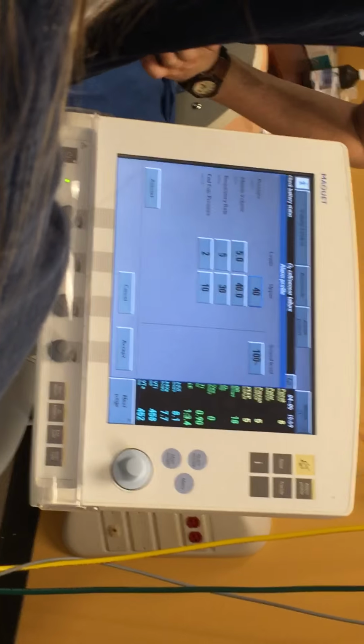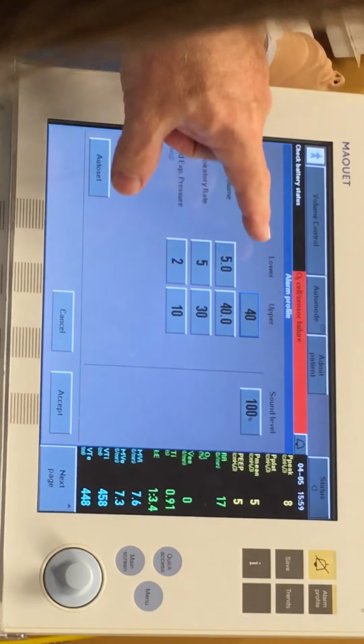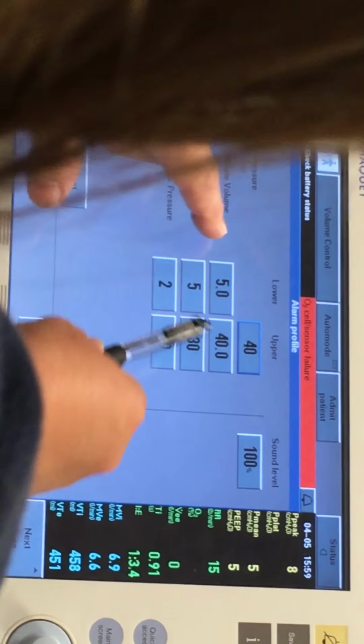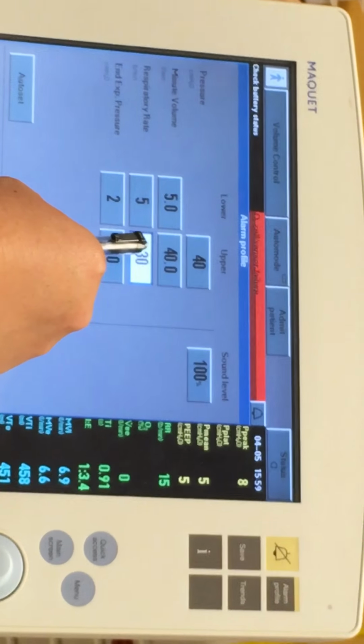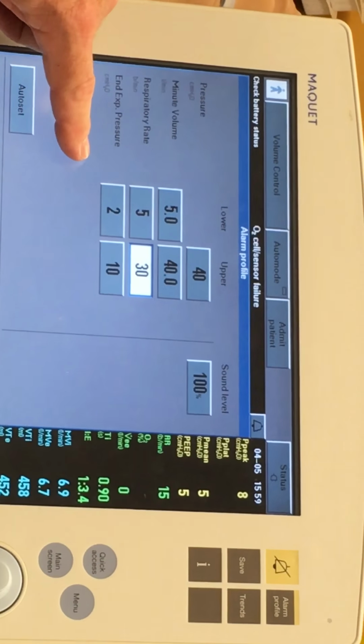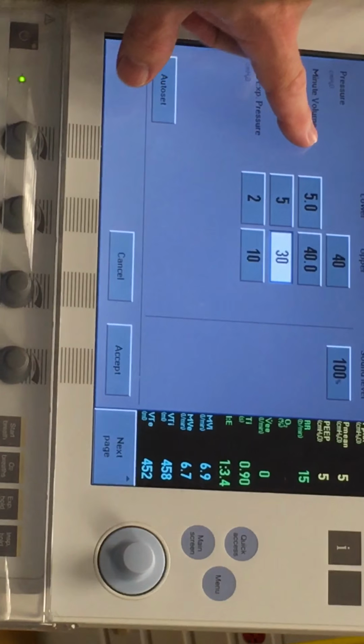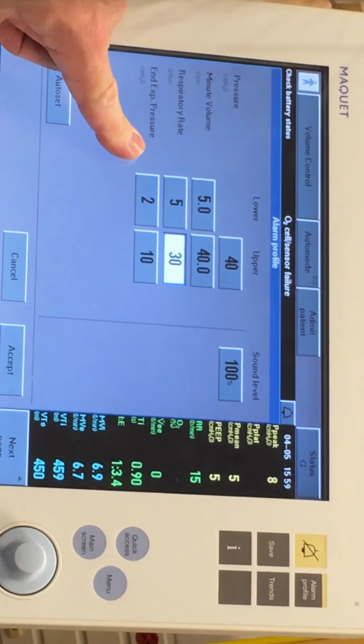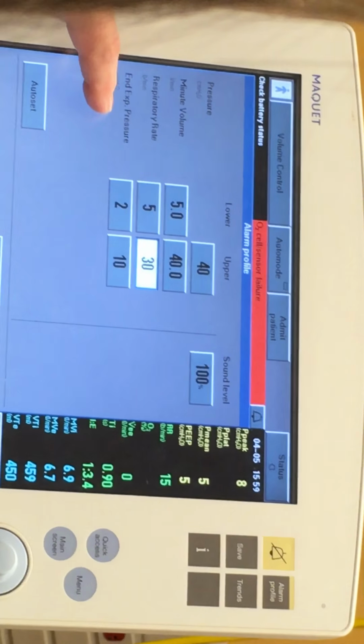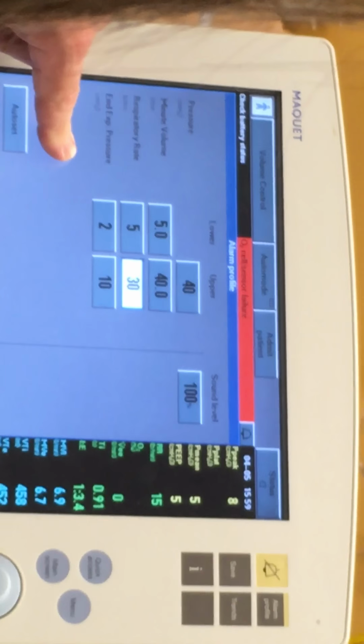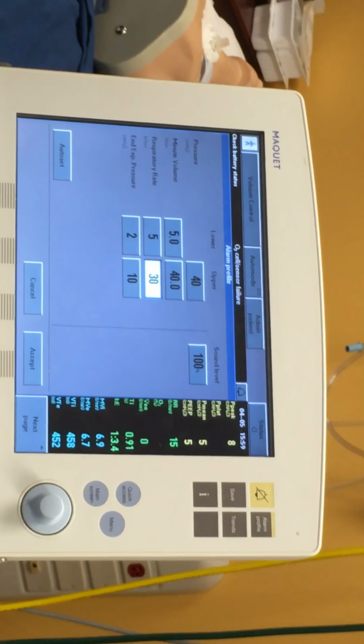And that's here on this one. Now this one you're not going to have all the alarms you're going to have on other ventilators. You don't have a low pressure alarm with this machine. So your disconnects on this machine are actually your low minute volume and your low PEEP. Expiratory pressure is the same as PEEP on this machine. Okay. So those two are your disconnects. It just has to be a little special. And you go over to the Avea, it's got alarms for everything.